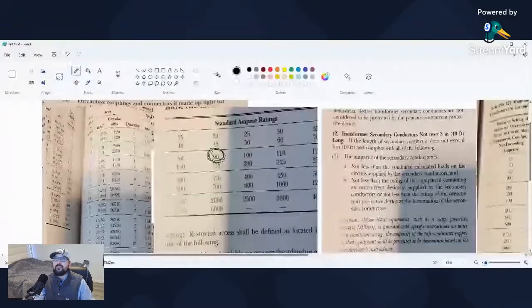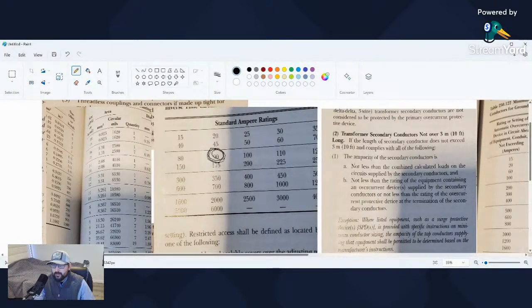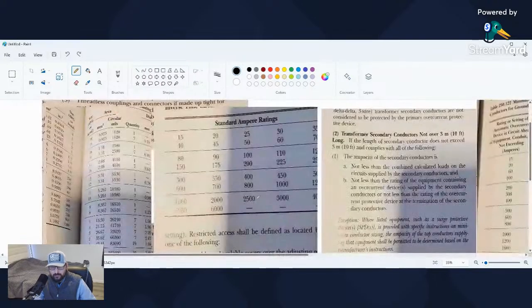So let's look at that real quick. Let's do this. Let's share. We are getting more used to this. Let's share this one here for the paint. And we're going to look right here. This image is so huge on this paint. Transformer secondary conductor is not over 10 foot long. If the length of the secondary conductor does not exceed 10 feet, it must comply with all the following.